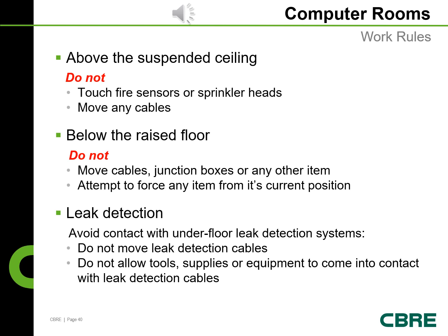Above suspended ceiling, do not touch fire sensors or sprinkler heads. Move any cables. Below the raised floor, do not move cables, junction boxes, or any other item. Attempt to force any item from its current position. Leak detection. Avoid contact with underfloor leak detection systems. Do not move leak detection cables. Do not allow tools, supplies, or equipment to come into contact with the leak detection cables.